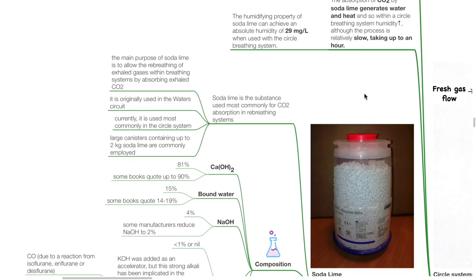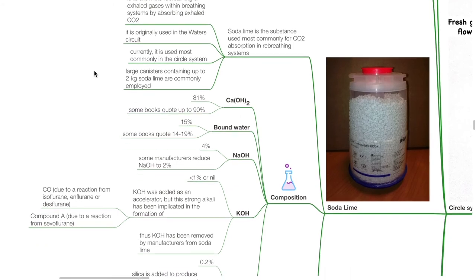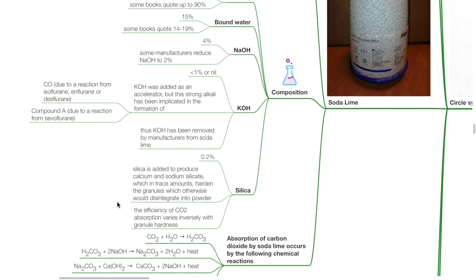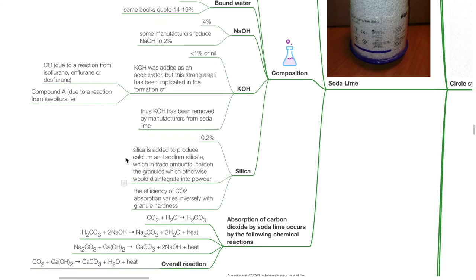Soda lime is the substance most commonly used for CO₂ absorption in rebreathing systems. Its main purpose is to allow rebreathing of exhaled gases by absorbing exhaled CO₂. Large canisters containing up to 2 kg of soda lime are commonly employed. Soda lime composition: Ca(OH)₂ 81%, bound water 15%, NaOH 4%, KOH less than 1% or nil. KOH was added as an accelerator but this strong alkali has been implicated in the formation of carbon monoxide from isoflurane, enflurane or desflurane, and compound A from sevoflurane — thus KOH has been removed by manufacturers. Silica 0.2% is added to produce calcium and sodium silicate which hardens the granules; the efficiency of CO₂ absorption varies inversely with granule hardness.